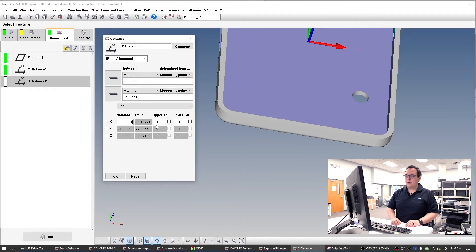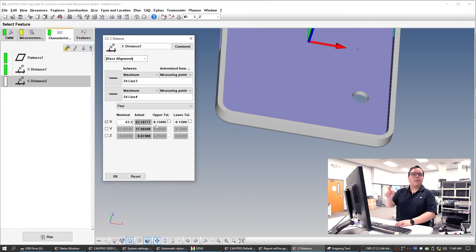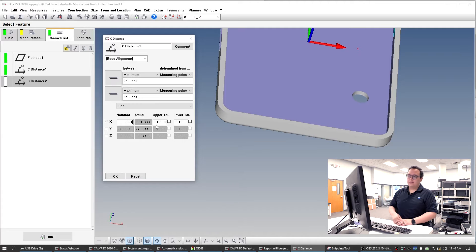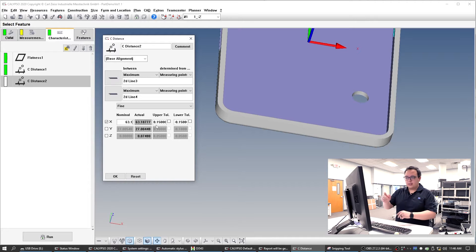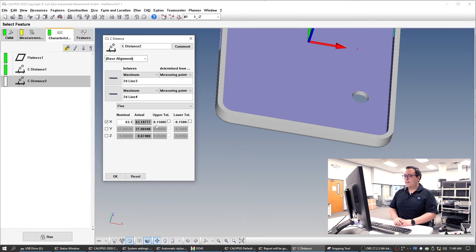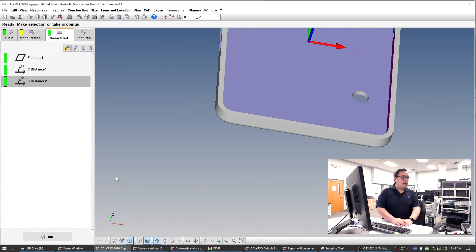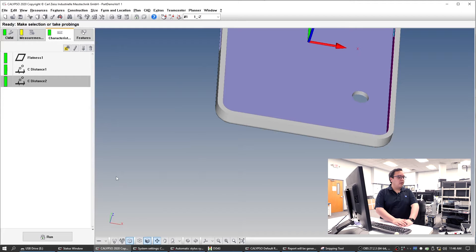It says it should be about 63.1 millimeters in the X direction. We'll give it some general tolerances — the general fine tolerance is going to be 150 microns. That should be good. And then what else did he ask for? He asked for the slot. So the slot — we actually have to make sure that we get that with the number three probe, or with the one going in the plus X direction.